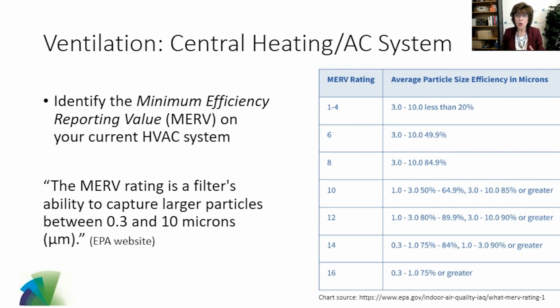Let's look at the chart on the right. MERV ratings are rated on a scale from 1 to 16, as determined by the Environmental Protection Agency. If you look at the MERV ratings from, say, 4 to 8, you can see the smallest particle they filter is 3.0 size microns.